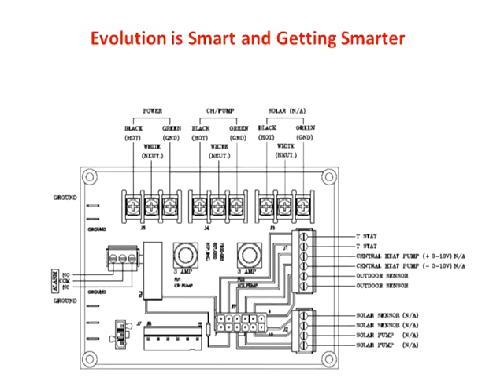This is actually for the future, NA, where you'll plug in the pump going out to the system, and that will then variably control it, rather than having a separate variable speed circulator. They'll actually be able to control that variable speed circulator on a variable basis right out of the control. The outdoor sensor hooks up neatly here. Over here will be, in the future, where your solar sensors and your solar pump go. So it's a very straightforward layout and very easily accessible.